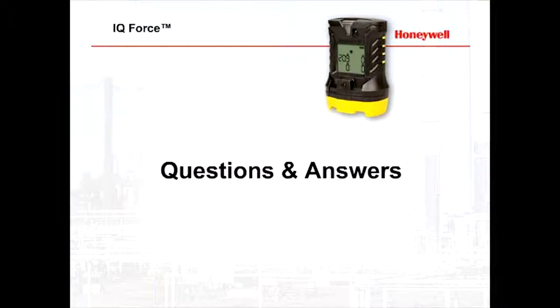Joe is asking a question about an end of sensor life indicator. Is there an end of sensor life indicator? So what you can do is use the IQ management software to give you a view of when that's coming up. With sensors like the oxygen sensor, they deplete over time, so the strength is just reducing over time. You can see that happening when you look at the sensor trending profile through the IQ management software. Now, you can't ever predict catastrophic failure in any sensor.